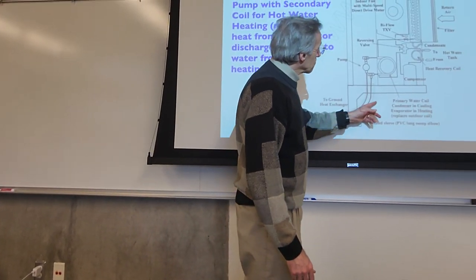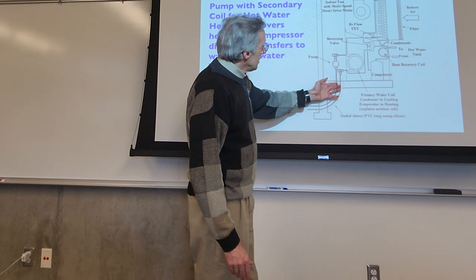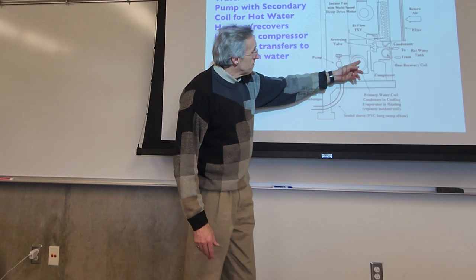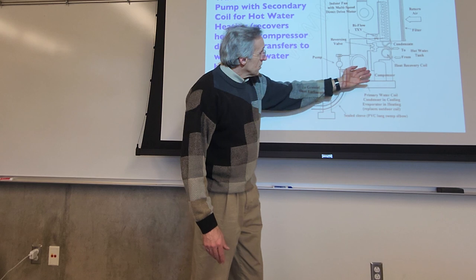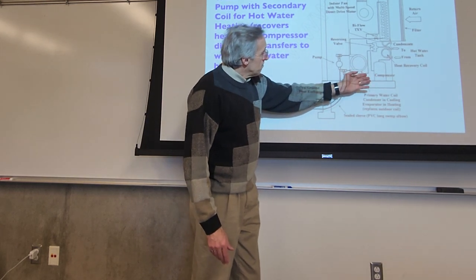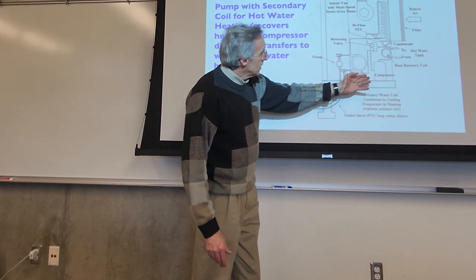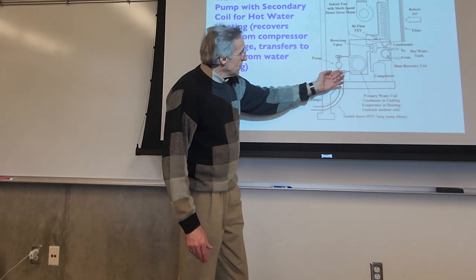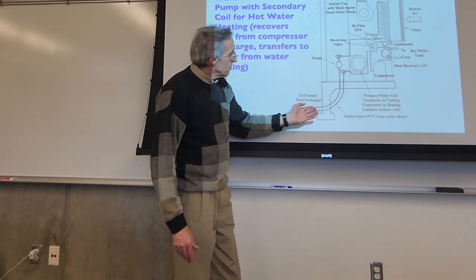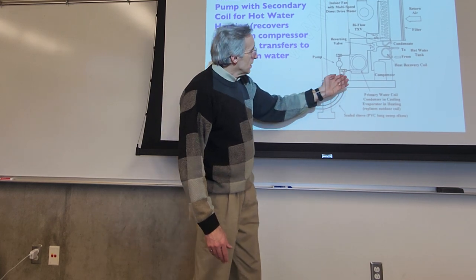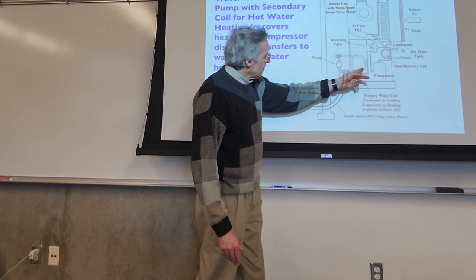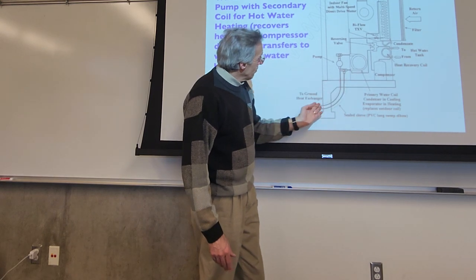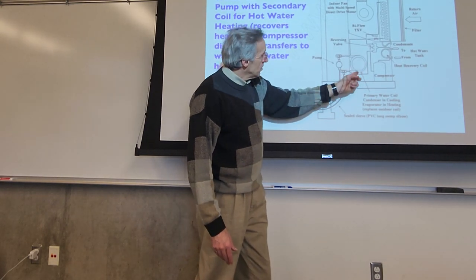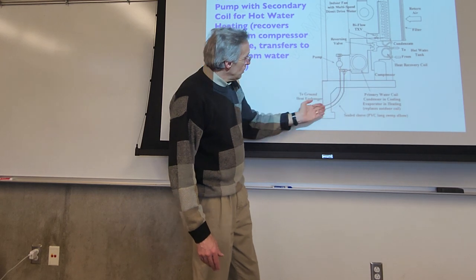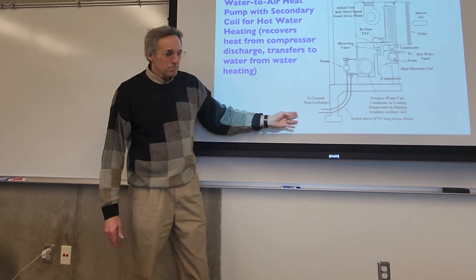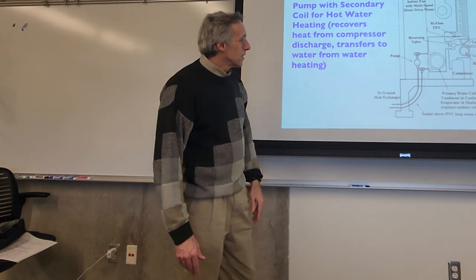And you bring that water in, and it exchanges energy with the refrigerant. So in cooling mode, the refrigerant would be rejecting heat to the water here, and in heating mode, this would be the evaporator, and energy would be going from the water into the refrigerant. So in the wintertime, you'd be refrigerating the water here. In the summertime, you're warming it up.